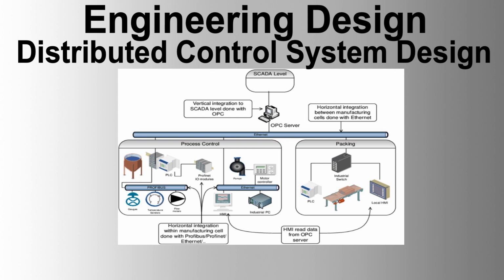Design and performance criteria. 1. General design requirements. The DCS design must ensure high reliability, availability, and maintainability. The system must support online modifications without interrupting operations. All components must be field-proven with successful operation in similar applications for a minimum period.